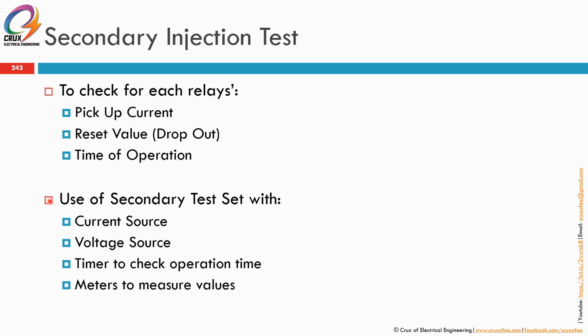What type of curve? Whether it's IEC, ANSI, IEEE, and so on. And the time setting multiplier, the time multiplier setting, TMS. So you can use a secondary test set with a current source or voltage source and a timer to check operation time, and meters to measure the values, the secondary current and so on. But these are the old style where you have to provide one by one. Nowadays you can just buy an Omicron or any China brand secondary injection test set, and everything is embedded there.